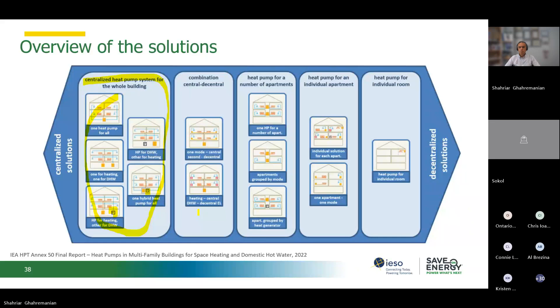So now I have every one of those situations here. For example, in solution one, heat pump for all, the benefit is very simple. It needs only one controller, and all the distribution and maintenance, everything, is going to be easier. But the negative aspect is high distribution losses, because we need distribution both for domestic hot water and for space heating. So the losses will be higher on that one.